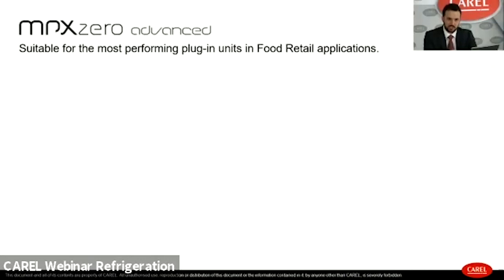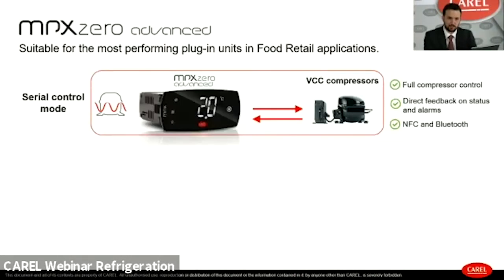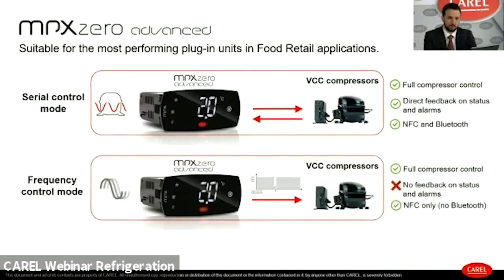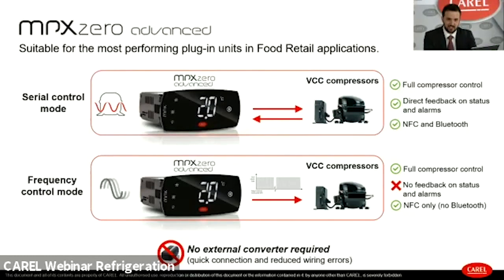For the most advanced plug-in units equipped with a variable capacity compressor, Carel provides two control modes. First is serial mode, where complete interaction and data exchange between the inverter and the MPXzero is guaranteed, including full compressor control and direct feedback on inverter status. The second option is frequency control mode through PWM output, where communication is one-way only, without the possibility to receive feedback on compressor status. Importantly, this controller does not need any external converter, which speeds up the connection and reduces wiring errors.